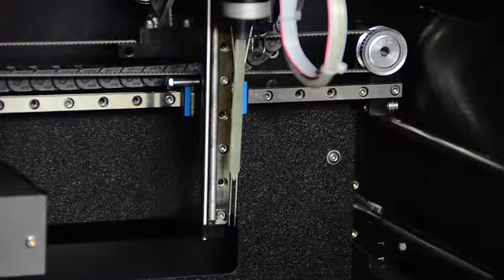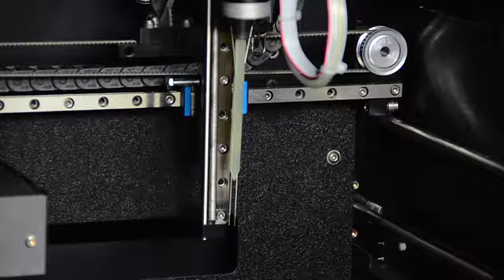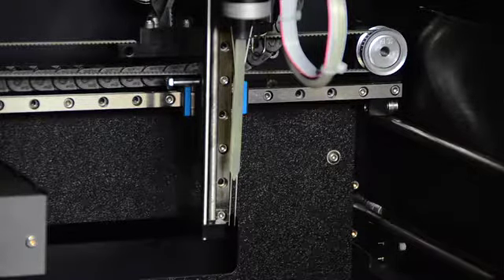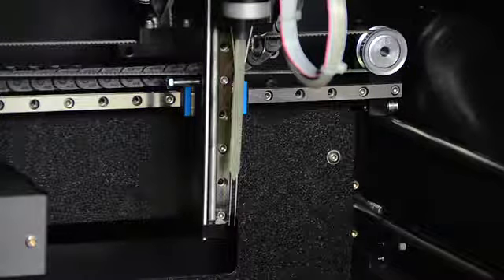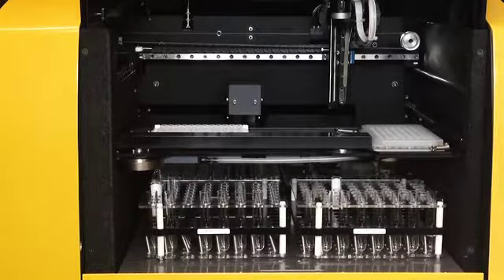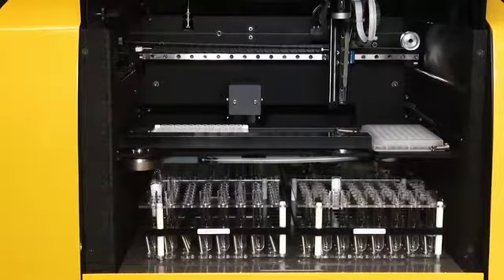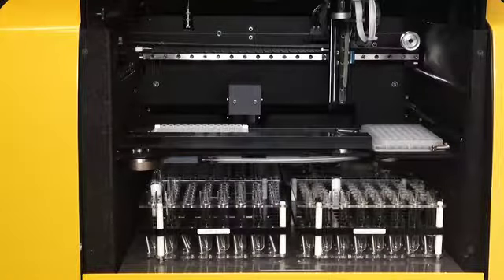This is a huge time savings. Like I said during the initial part of this demo, the other instruments have to move diluent, move the sample, mix that, then transfer to the plate. In comparing to the Dynex instruments, we do what they take an hour to do in 15 minutes. For all diluted tests, there's a large number of tests out there, especially in clinical labs, that require dilutions. We save a whole lot of time up front with those tests. And I just want to emphasize that feature because that is a very big selling point for our instrument.